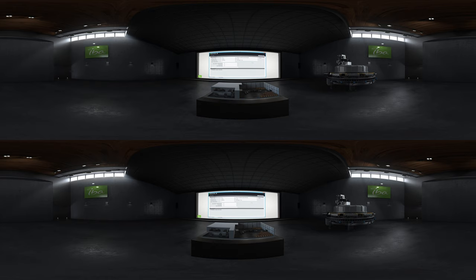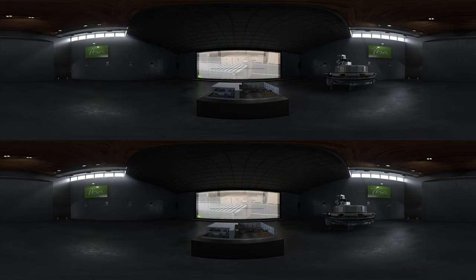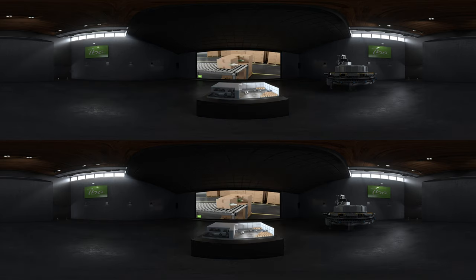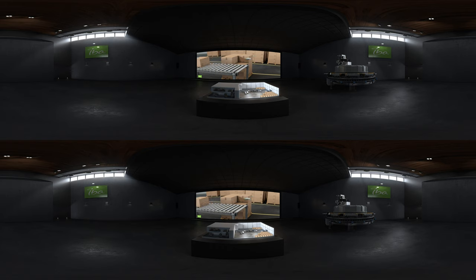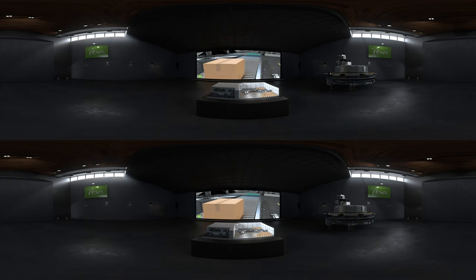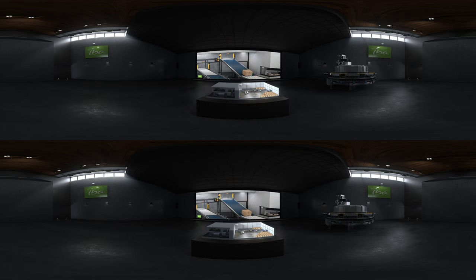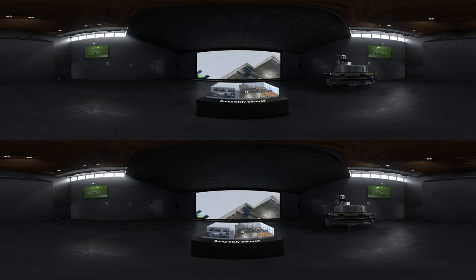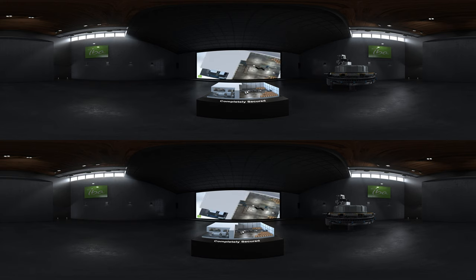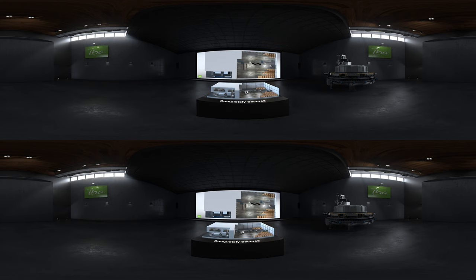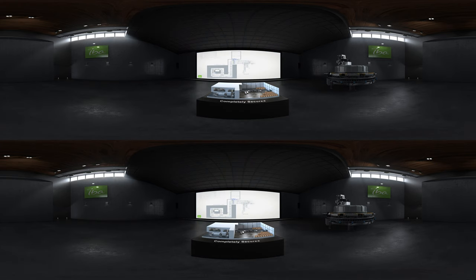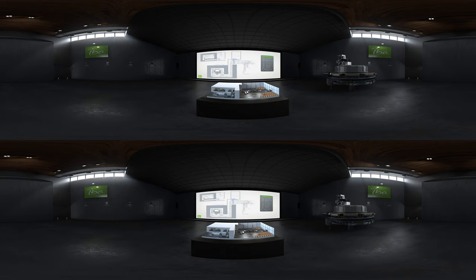After the validation of the batch order, the first box can be loaded. In order to track and identify the boxes during the process, each of them receive its own label. Dosimeters are also placed on some boxes to confirm the validation of the treatment by measuring the irradiation dose. The boxes are then sent inside the vault. The irradiation and Rhodotron vaults are completely secured to avoid anybody entering during the operation. To secure this area, different devices are installed to detect any intrusion that would automatically shut down the Rhodotron. In parallel, radiation level is monitored in both vaults at any time.